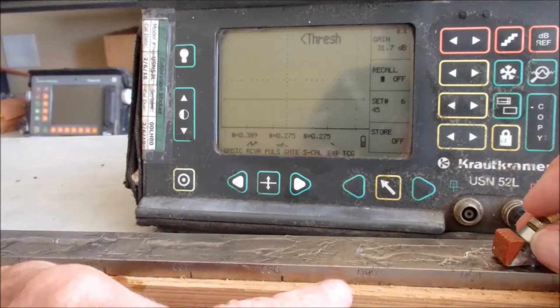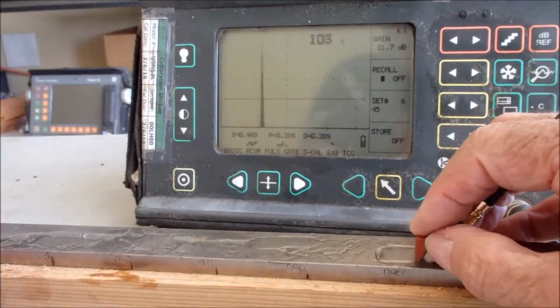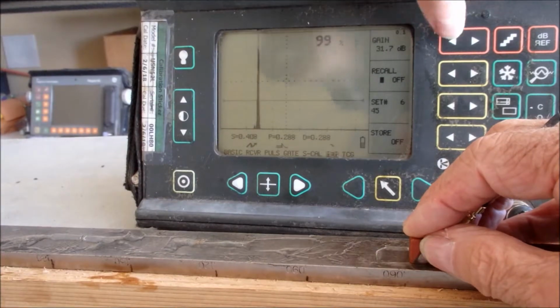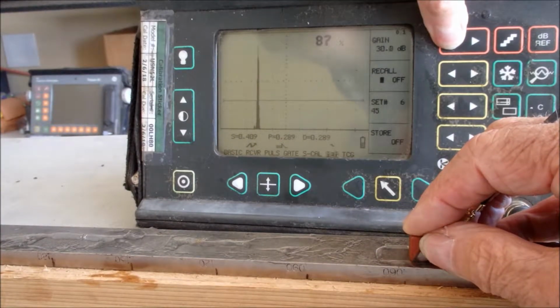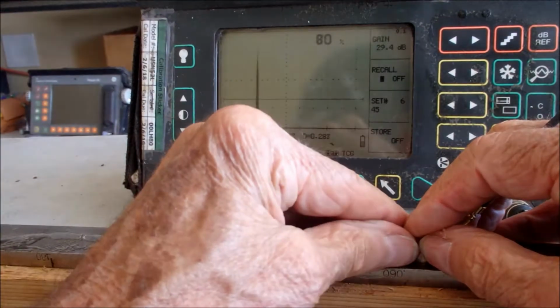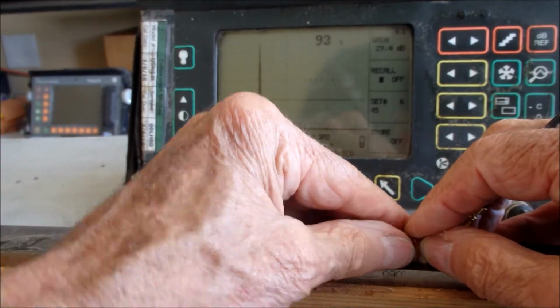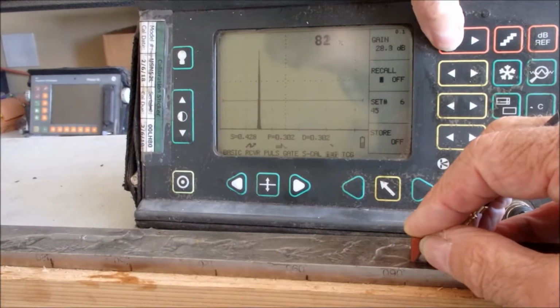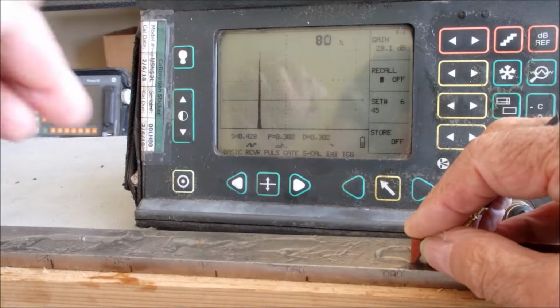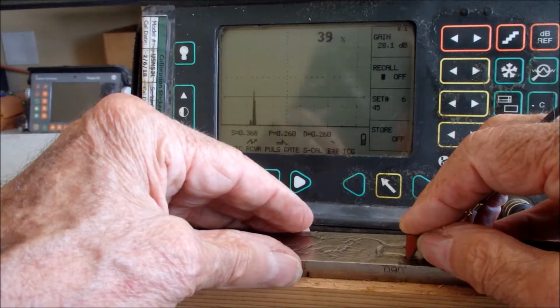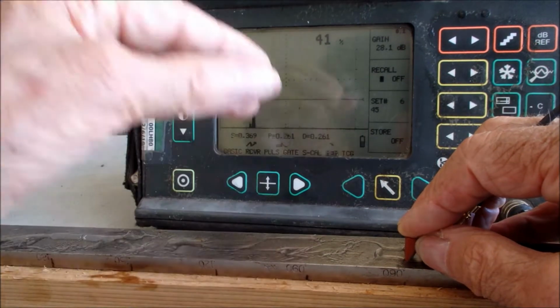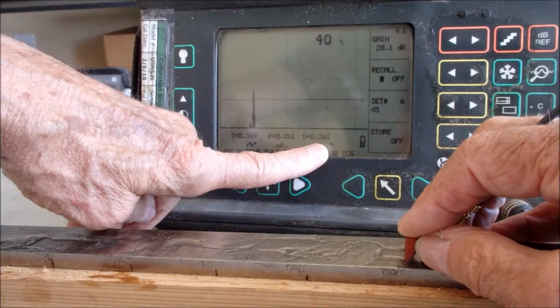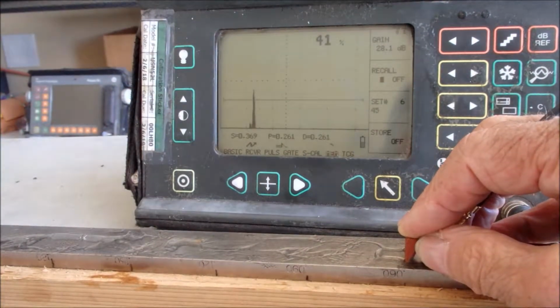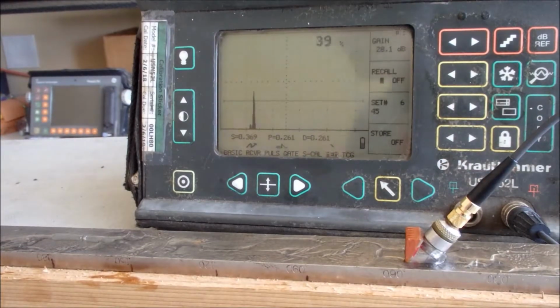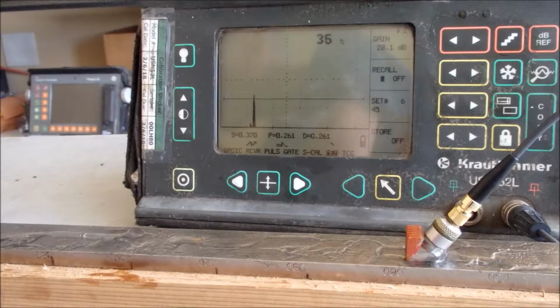All right, let's try the 60 thou notch. There's our loud corner trap signal. We'll bring that down to 80% screen height. Maximize that. All right, there's 80%. I'm going to push forward till that is 40%. That'd be a 6 dB drop. Right about there. That's saying 261. 300 minus 261 is 39 thousandths. That is 60, but that technique says it's 39.